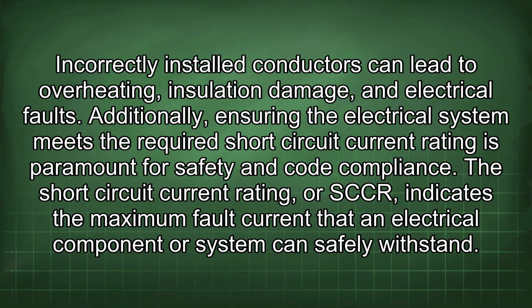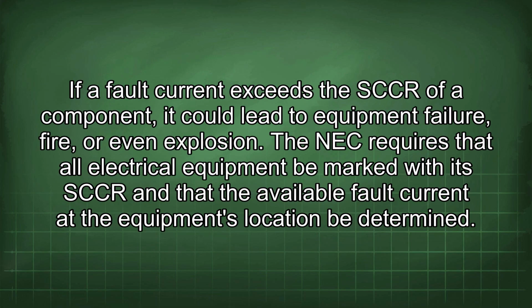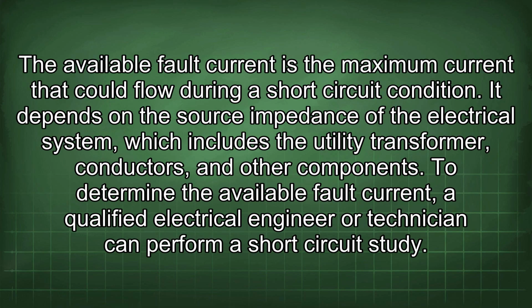Additionally, ensuring the electrical system meets the required short-circuit current rating is paramount for safety and code compliance. The short-circuit current rating, or SCCR, indicates the maximum fault current that an electrical component or system can safely withstand. If a fault current exceeds the SCCR of a component, it could lead to equipment failure, fire, or even explosion. The NEC requires that all electrical equipment be marked with its SCCR and that the available fault current at the equipment's location be determined. The available fault current is the maximum current that could flow during a short-circuit condition.